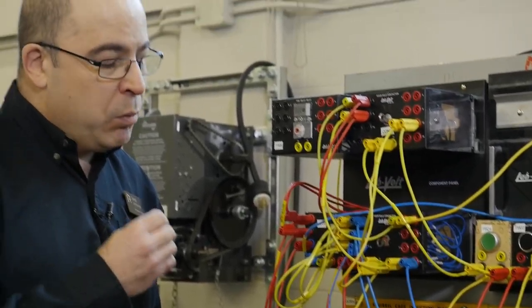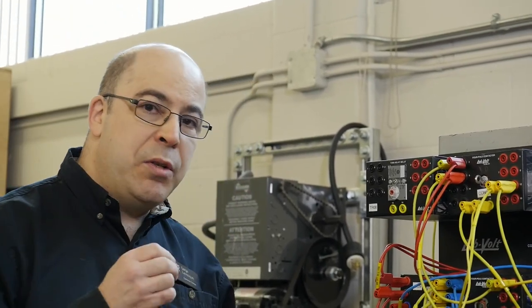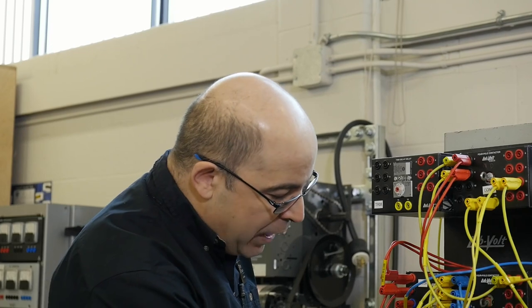The eddy current brake, what we're going to do is we're going to run DC current through the windings in the stator and we're going to create a DC magnetic field that will interact with the rotor of the machine to bring it to a very quick stop.